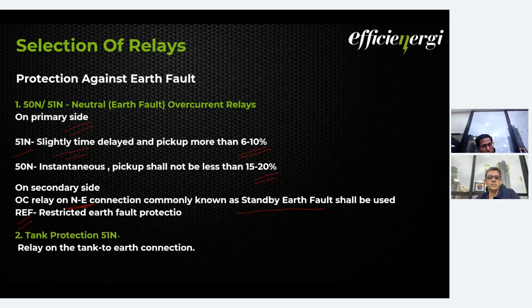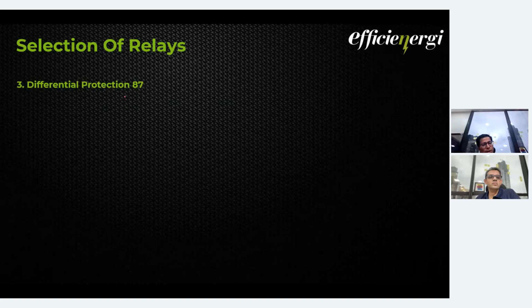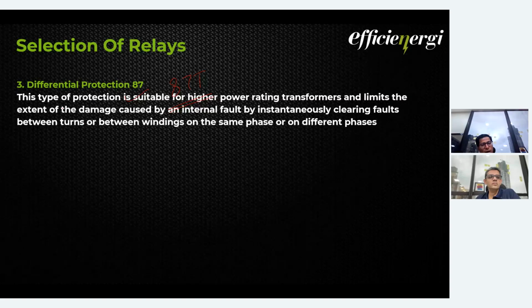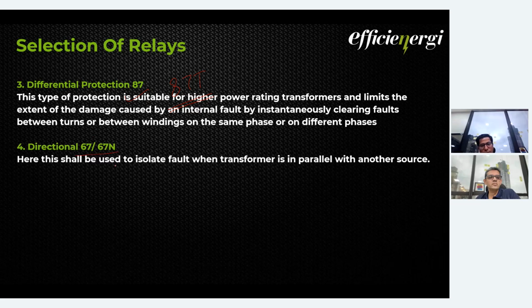Then there is tank protection. Basically, the earth connection between tank and earth. In that bus bar, we put the CT and take this to a 51N relay. Again, the differential protection 87T you all must be knowing. Then directional, where the transformer is in parallel with another source. If two transformers are running in parallel, you have to consider directional 67.